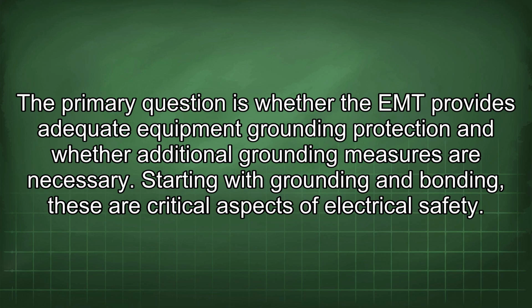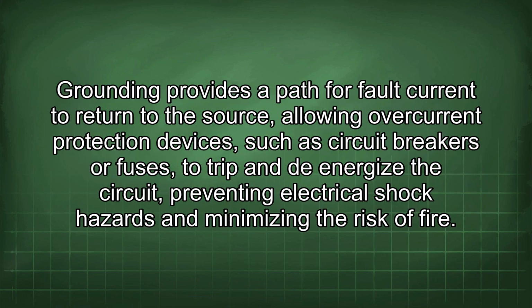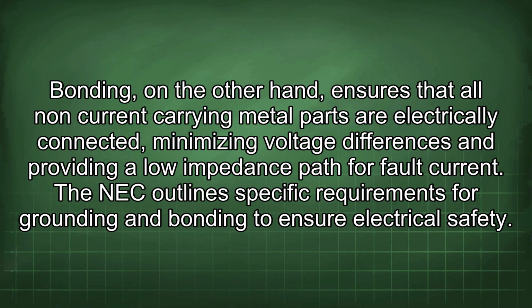Starting with grounding and bonding, these are critical aspects of electrical safety. Grounding provides a path for fault current to return to the source, allowing overcurrent protection devices such as circuit breakers or fuses to trip and de-energize the circuit, preventing electrical shock hazards and minimizing the risk of fire. Bonding, on the other hand, ensures that all non-current carrying metal parts are electrically connected, minimizing voltage differences and providing a low impedance path for fault current.